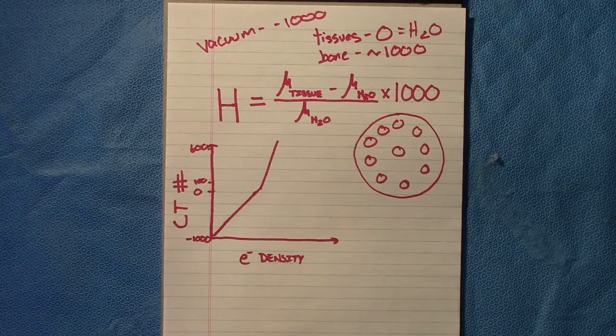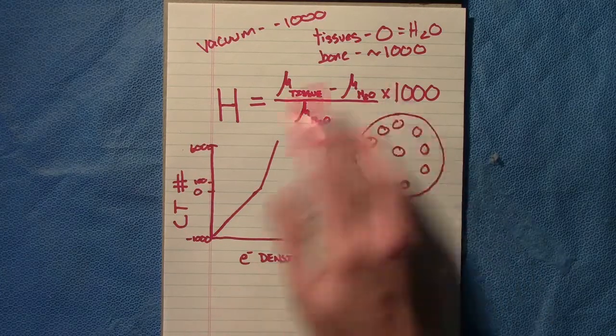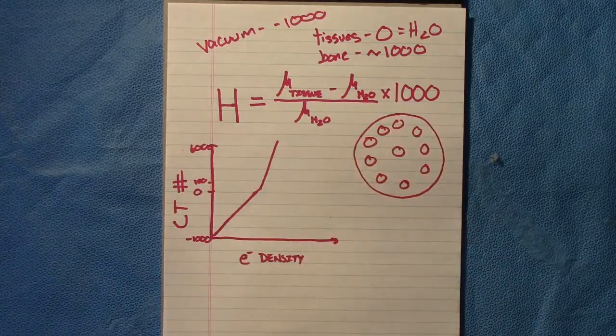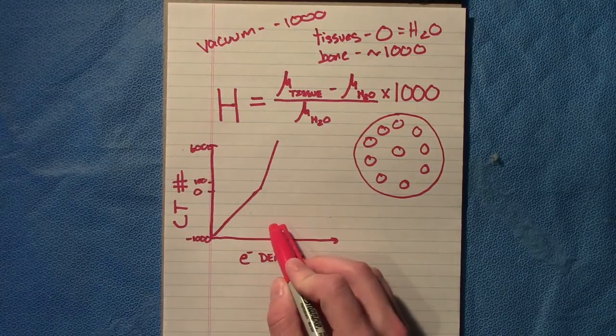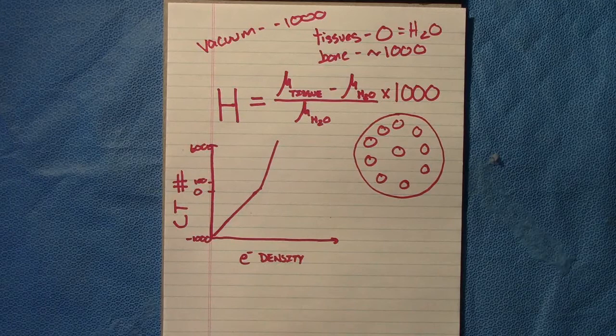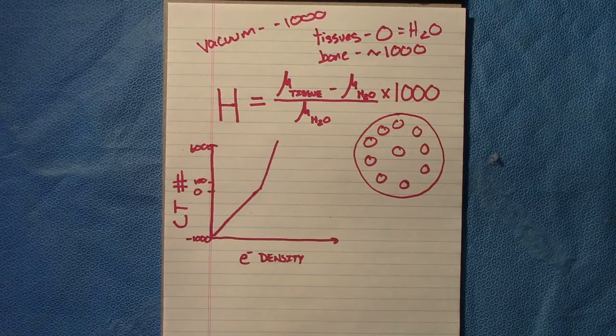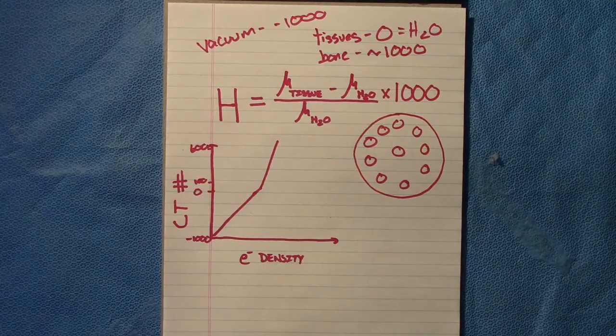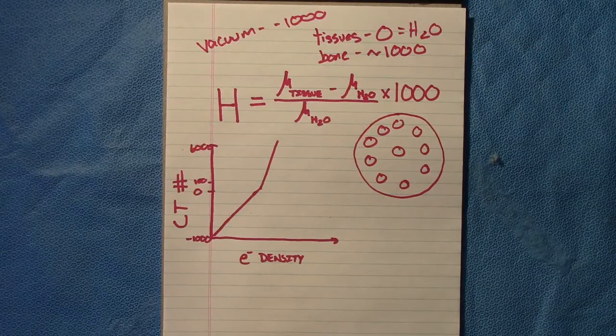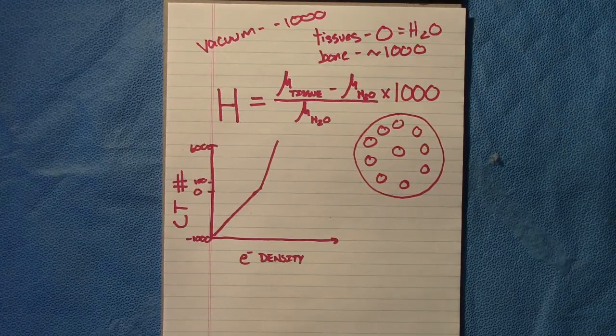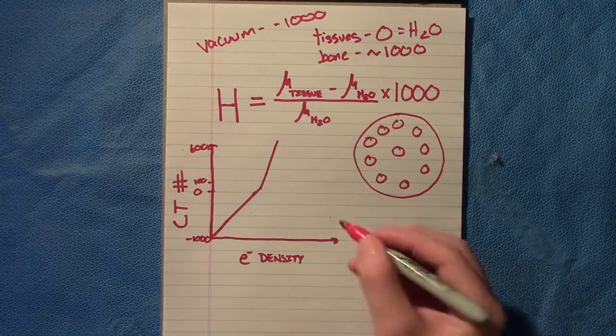All of this is a very crucial step in radiotherapy because if this curve is incorrect, then you are miscalculating dose to a certain percentage on every time that you're calculating dose, whether it's a phantom or an actual patient. So that is why we have QA to test for CT.